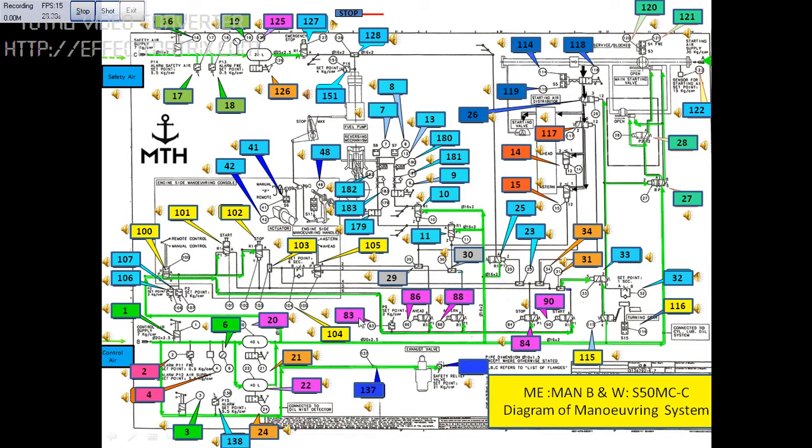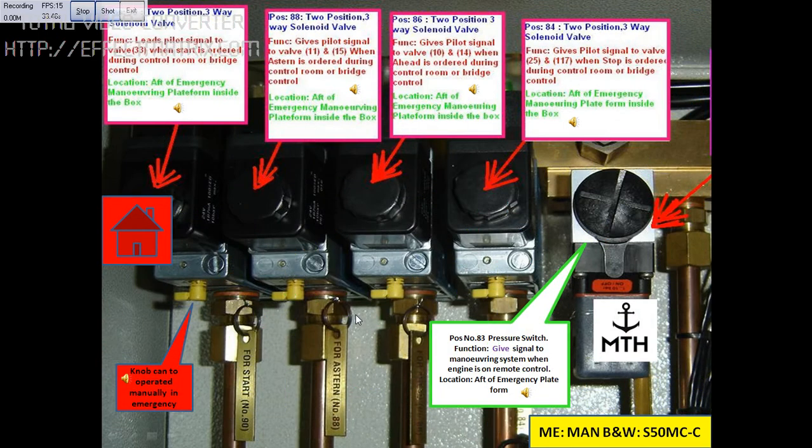I will click on the icon to go to the real picture on the ship. This component is position number 90, which is a two position three-way solenoid valve. The function of this block is to lead pilot signal to valve number 33 when start is ordered from control room or bridge control.